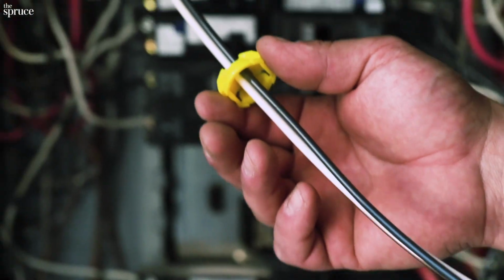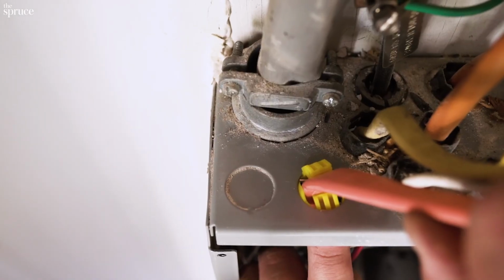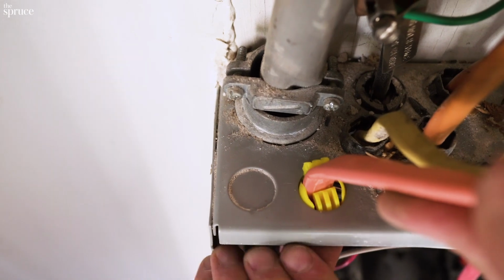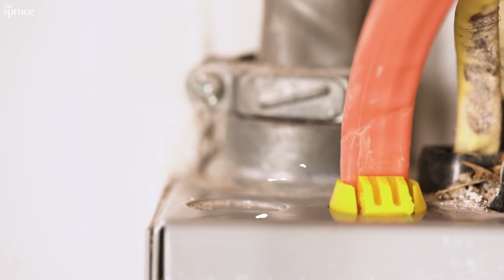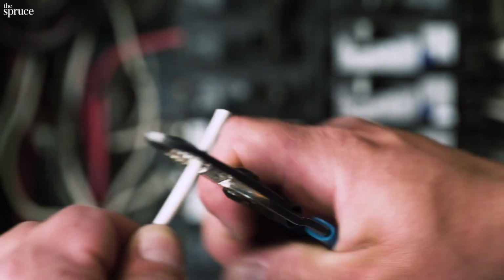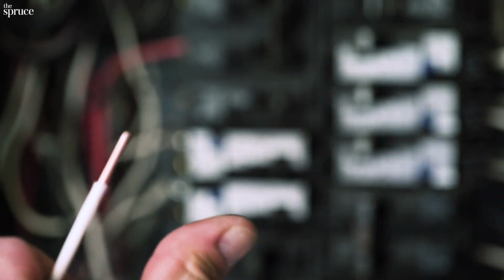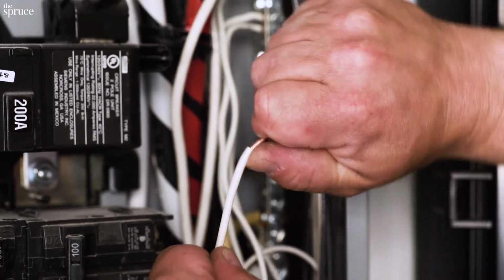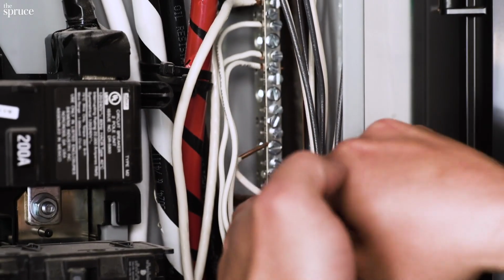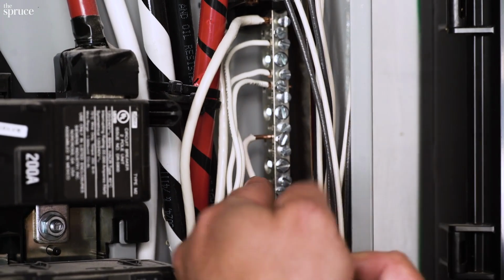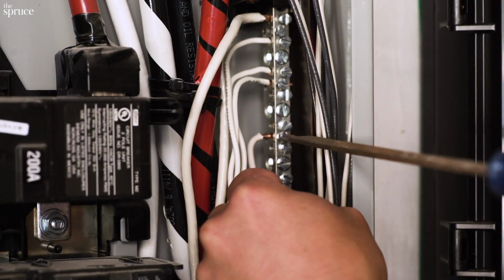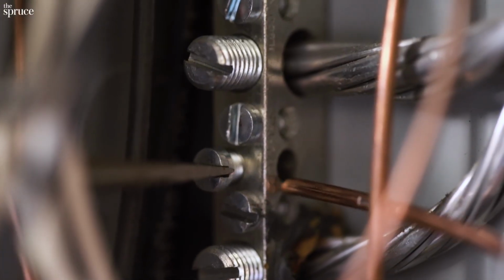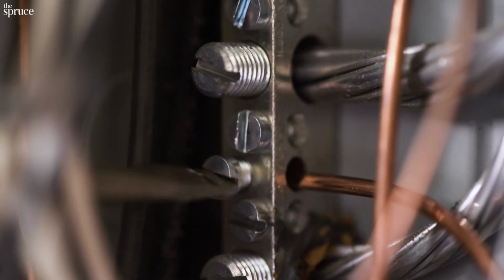Once your wire is stripped, slide this little plastic knockout clip over your cable and snap it to your box so it secures the cable. Now let's trim, strip, and connect the wires. You bend the white neutral wire and slide it into the terminal slot on the neutral bus bar. It has to be an open slot. In other words, you can't put 2 wires under the same terminal. The ground wire slides in and gets secured into the ground bus bar in the exact same way.